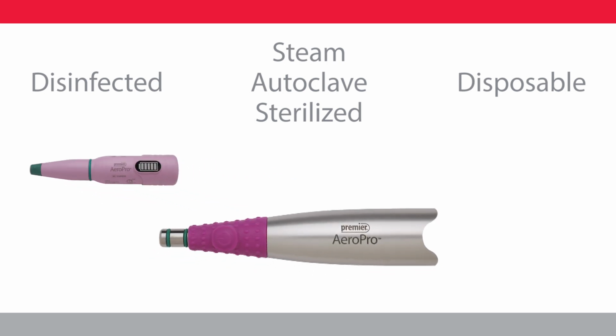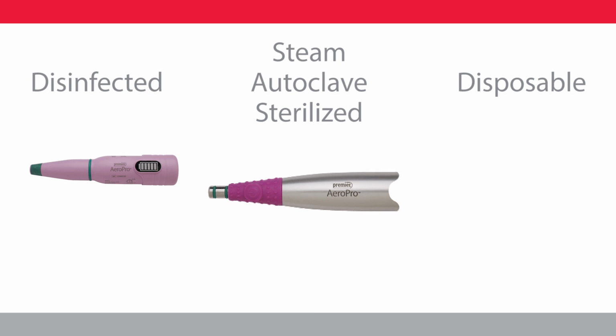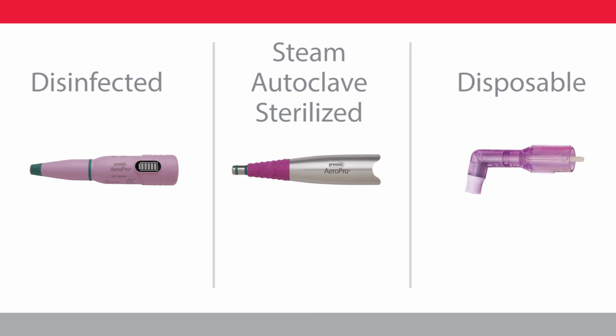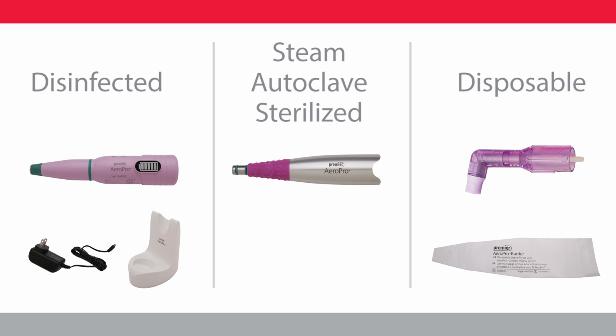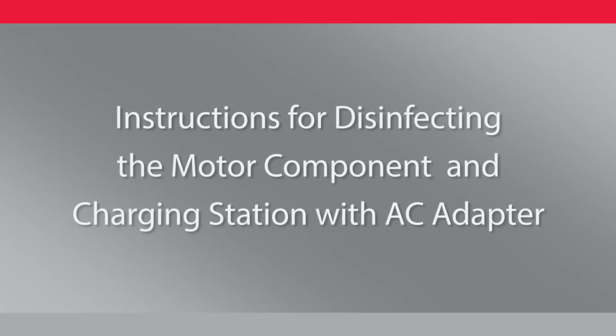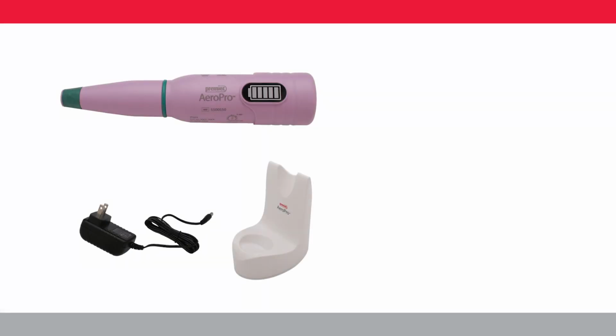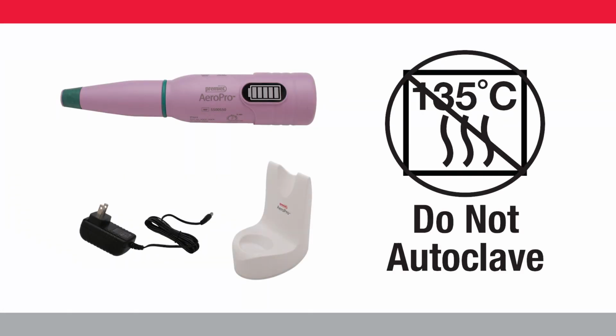The outer sheath that protects the motor component is steam autoclaved. Both the disposable Prophy angle and custom polyethylene barrier are single-use items and are discarded after each treatment. The charging station with AC adapter are disinfected, and the included tray stand is steam autoclaved. The motor component, charging station, and AC adapter cannot be steam autoclaved and need to be disinfected.